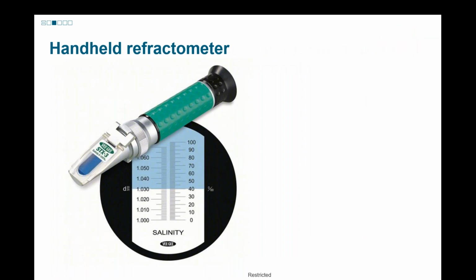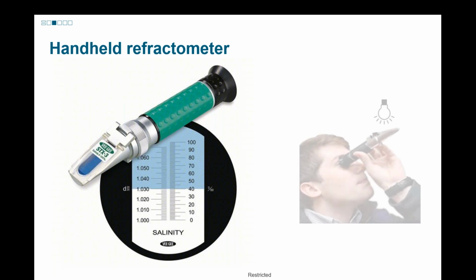So here is what is commonly used in the industry. It's a handheld refractometer. Now this is going to be used just to take a spot check. It's not in line. It's a spot check of what's going on. You take a sample out of the process and you place it on the surface, and you can now hold it up to the light and read what the concentration is in your process. But there's a few potential problems.